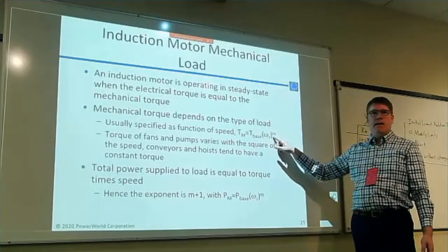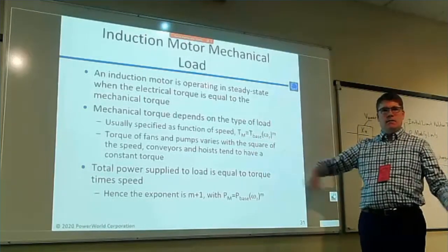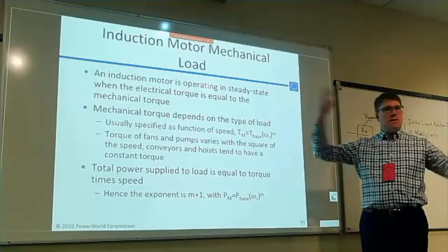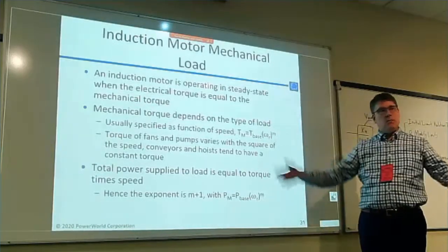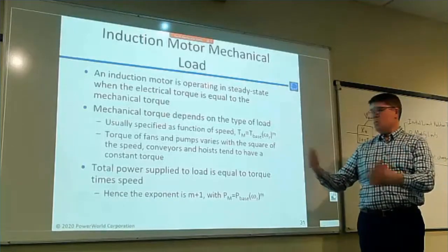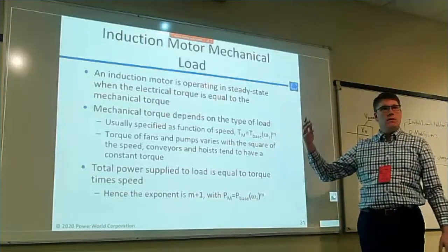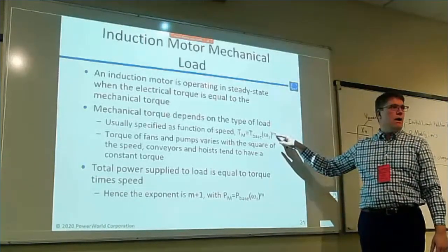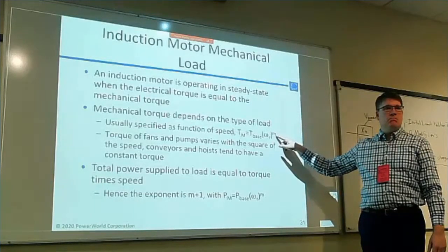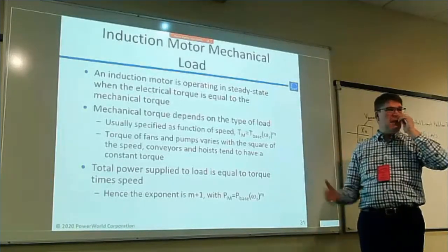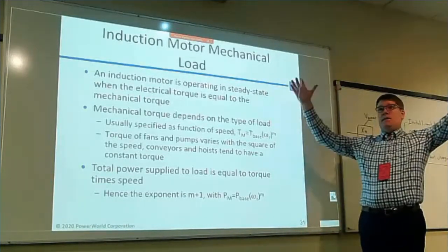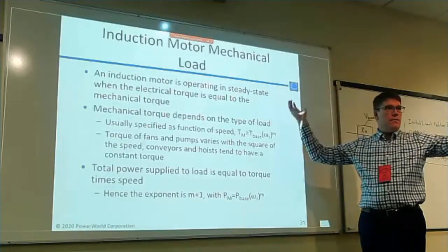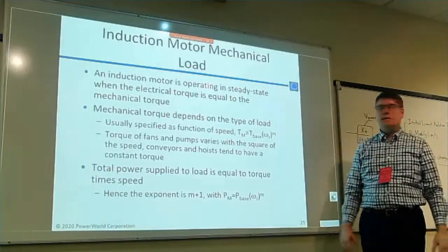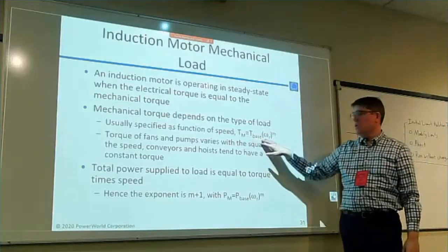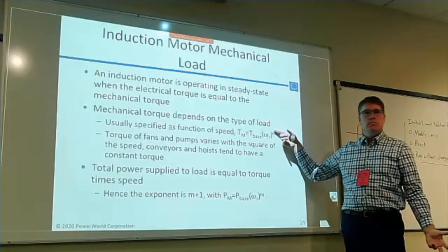If it's a fan, think about it: the faster it spins, it's got a big inertia because it has big blades. It takes more and more torque as speed increases, and I believe it ends up being the square. So in a manufacturing plant with giant fans pulling air out of an industrial process, you'll have a motor load where the exponent is 2.